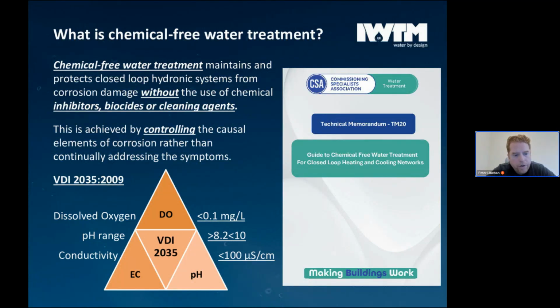Corrosion is an electrochemical process. So you want to get the electrical conductivity of your water to be as low as possible. You want it below 100 microsiemens. And effectively, if you get it below that level, it means the dissolved oxygen ions in the water cannot travel around as fast as if it were at a higher level. So getting it down as low as possible means the dissolved oxygen ions cannot travel very fast around the system, effectively lowering and slowing your corrosion rate.